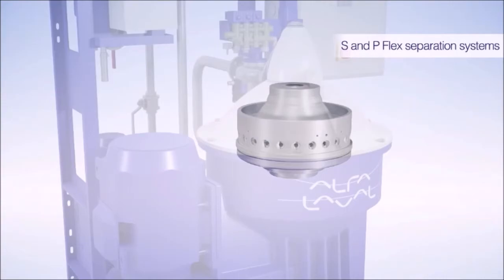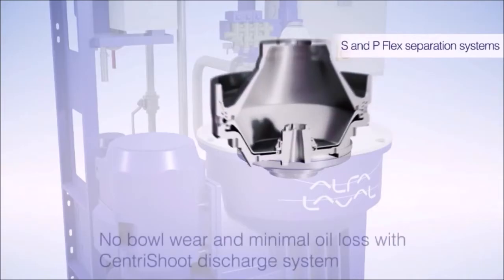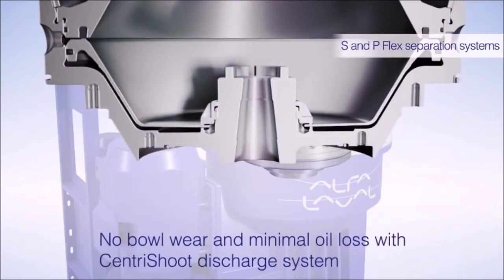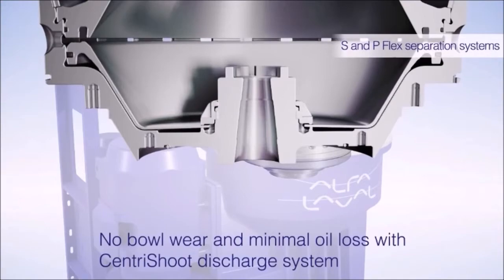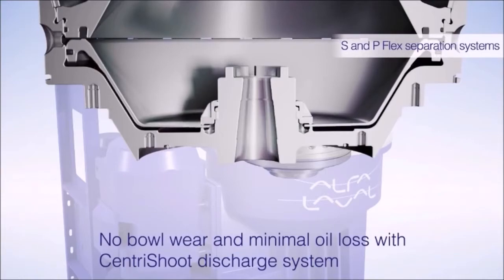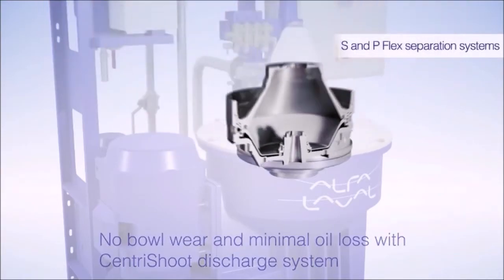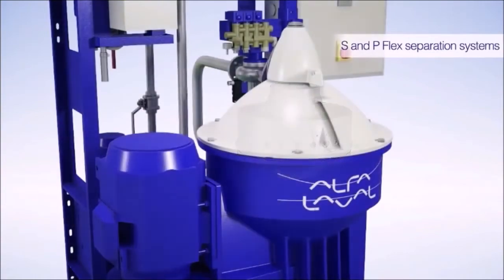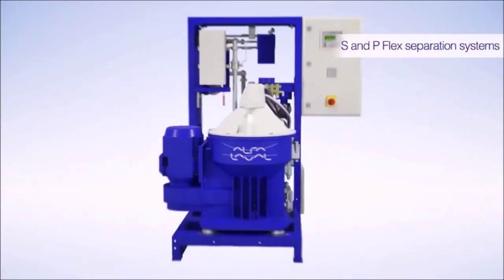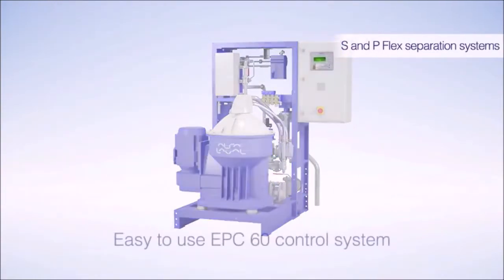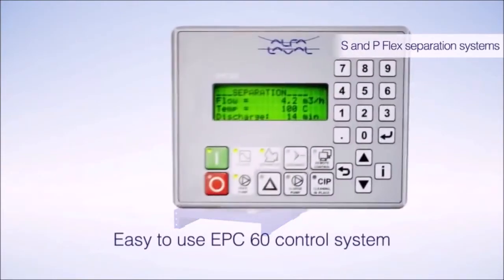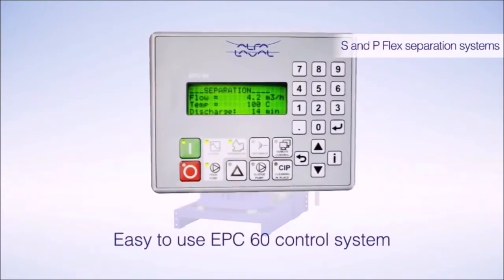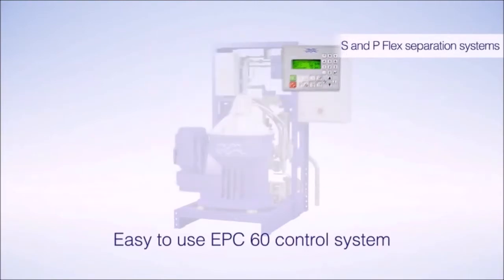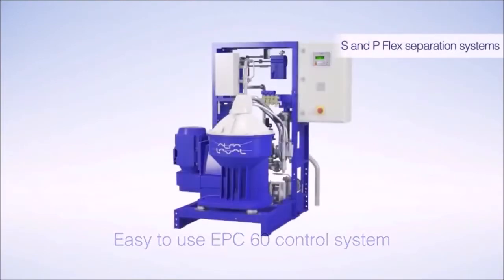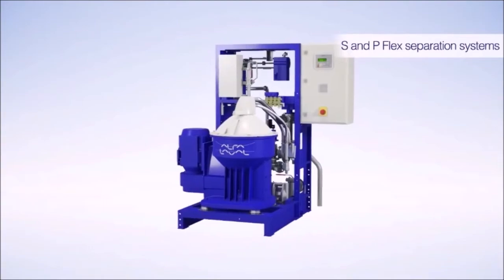Maintenance: the bowl and disc stack will require periodical cleaning whether or not an ejection process is in operation. Care should be taken when stripping down the bowl, using only the special tools provided, and noting that some left-hand threads are used. The centrifuge is a perfectly balanced piece of equipment rotating at high speed, so all parts should be handled and dried with care.